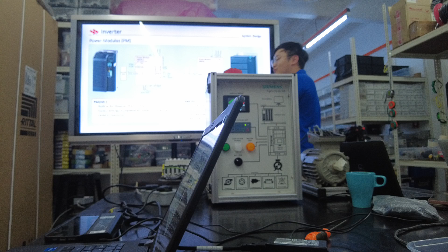One option, we use a PM250. The external energy can feed back to the supply line, no waste, and also reduce harmonics. But this model is really obsolete, too many issues, it always burns on the side.